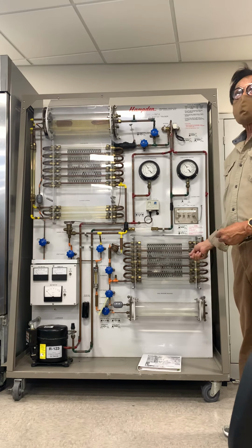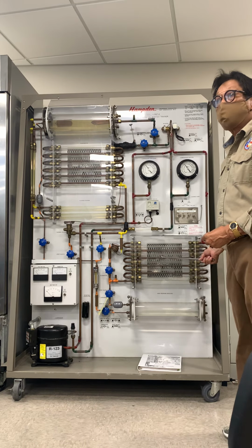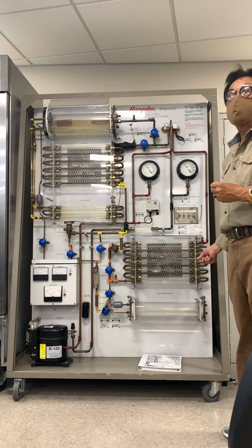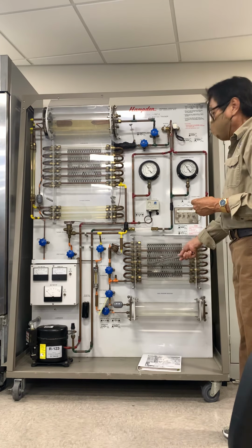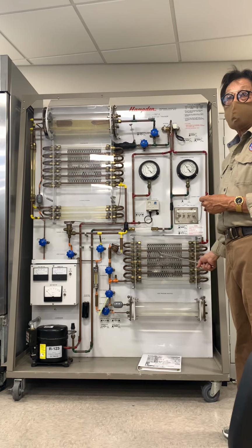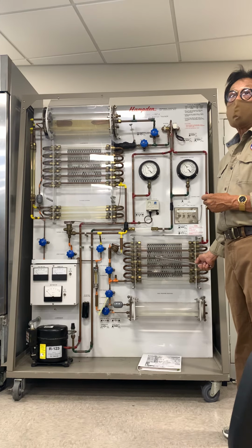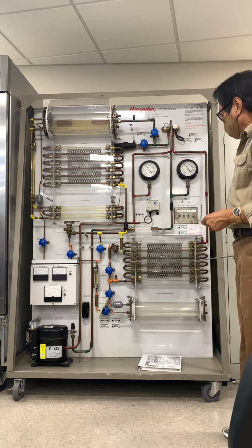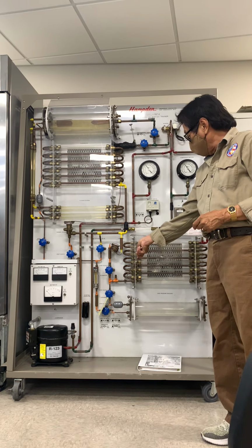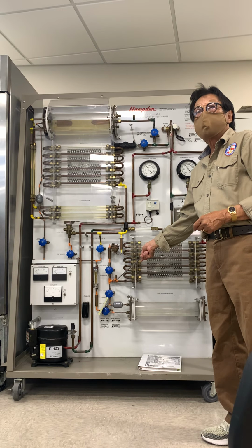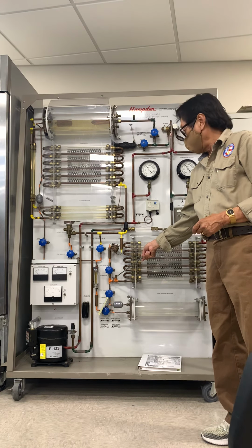By the time it reaches the middle part of the condenser, the refrigerant would all be in total high pressure, high temperature liquid form. But there are still a few tubes left before it can come out. That is where the refrigerant is subcooled. By the time the refrigerant leaves the condenser, it would be in total pure high pressure, high temperature liquid.